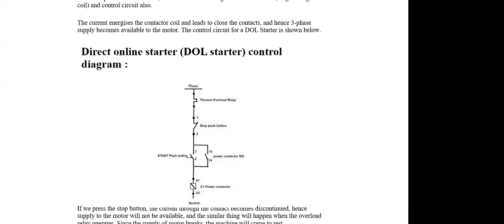Now the consideration is, this particular timing is based on the time required for the induction motor to reach its synchronous speed. Synchronous speed is what? If I am running a 4-pole motor, it is 1500 RPM. So from zero, from no running to 1500 RPM, if it is taking say 50 milliseconds, 75 milliseconds, then that is the time this starting current will sustain.